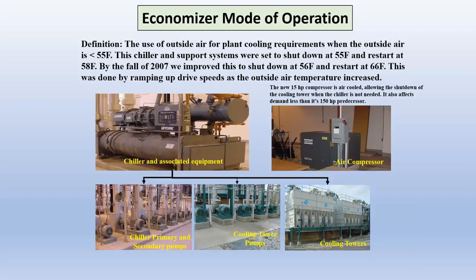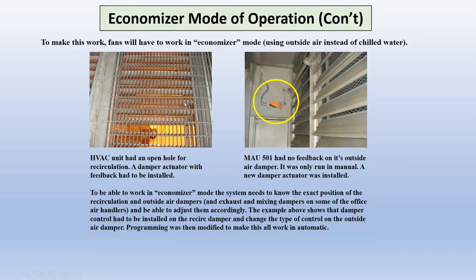Very powerful tool. When you're setting up to economize, obviously you want to set up so this chiller isn't needed. There was one load in the plant, other than the air handlers, that was on chilled water, and that was the air compressor. And it was oversized anyway, so I just put an air-cooled air compressor in, and then I was able to shut down this chiller and economize. So to make an economizer work, you had to make sure that you had modulating dampers, the outside air damper and the return air damper, and exhaust damper. Those needed to work and to be able to modulate to determine how much outside air you're going to bring in. So all that feeds back to the BAS, and the BAS has to control all that. And the economizer sequence of operations.